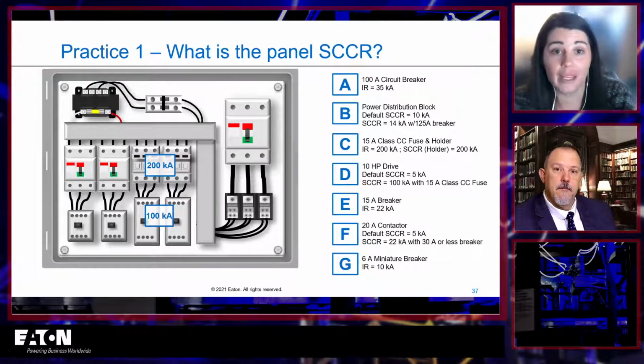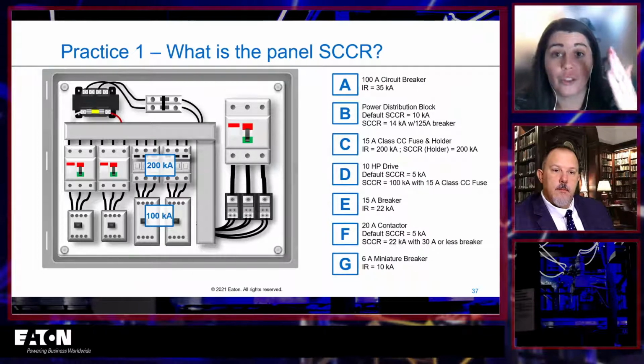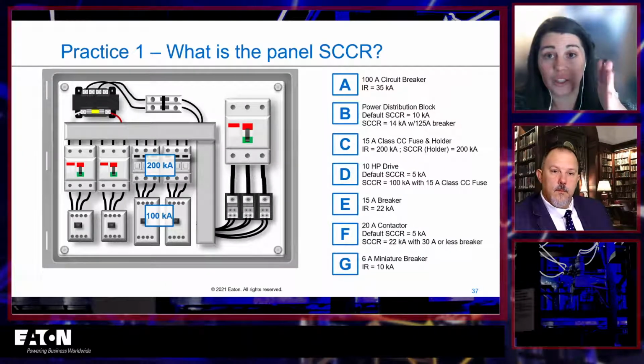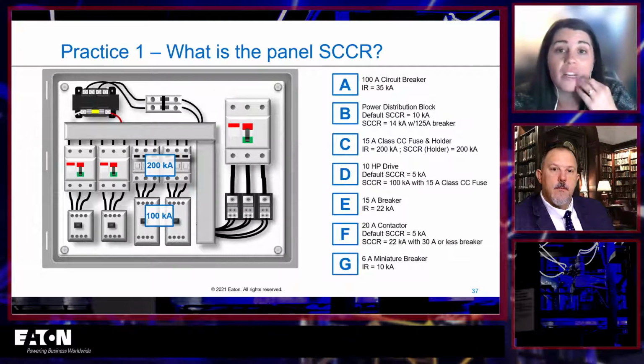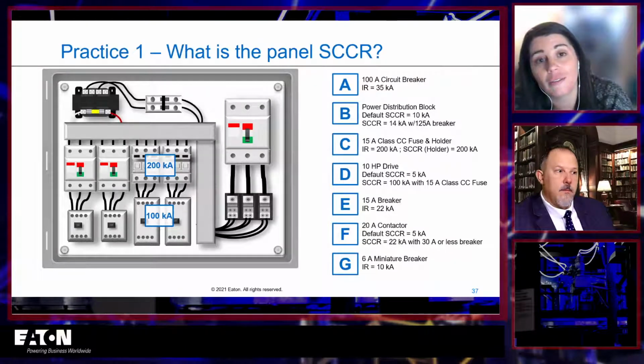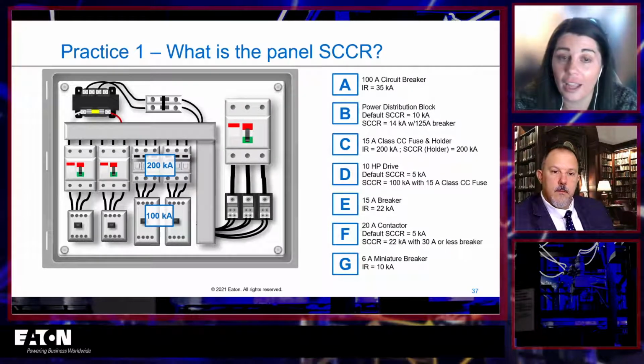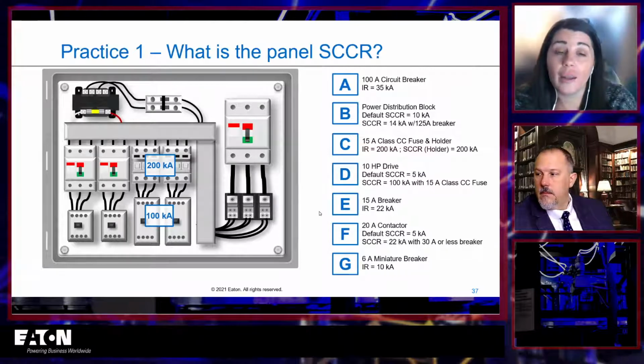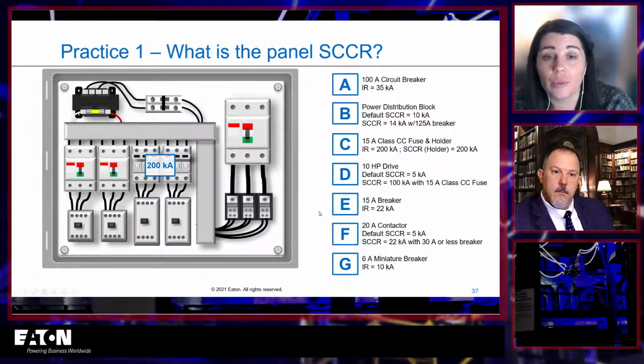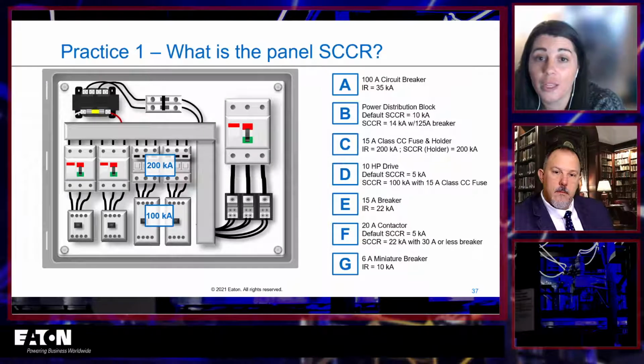Great. That means my short circuit current rating of that branch is going to be the lowest value of the short circuit current rating or interrupting rating in there. So my branch short circuit current rating here is going to be 100 kA. And then I'm going to go ahead and look at the next branch. This would be EF, my breaker plus contactor.